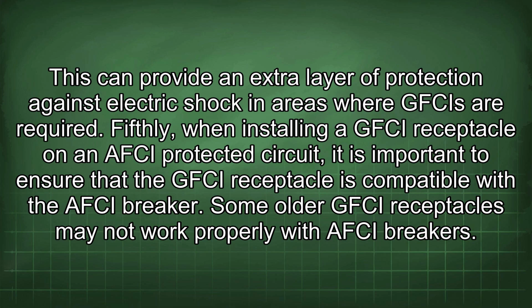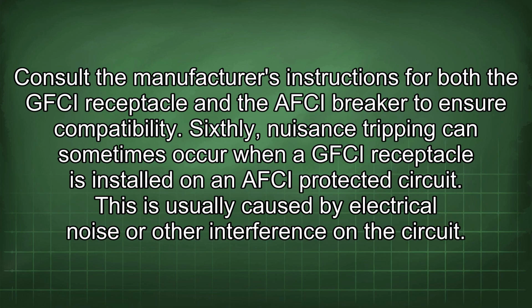Fifthly, when installing a GFCI receptacle on an AFCI protected circuit, it is important to ensure that the GFCI receptacle is compatible with the AFCI breaker. Some older GFCI receptacles may not work properly with AFCI breakers. Consult the manufacturer's instructions for both the GFCI receptacle and the AFCI breaker to ensure compatibility.